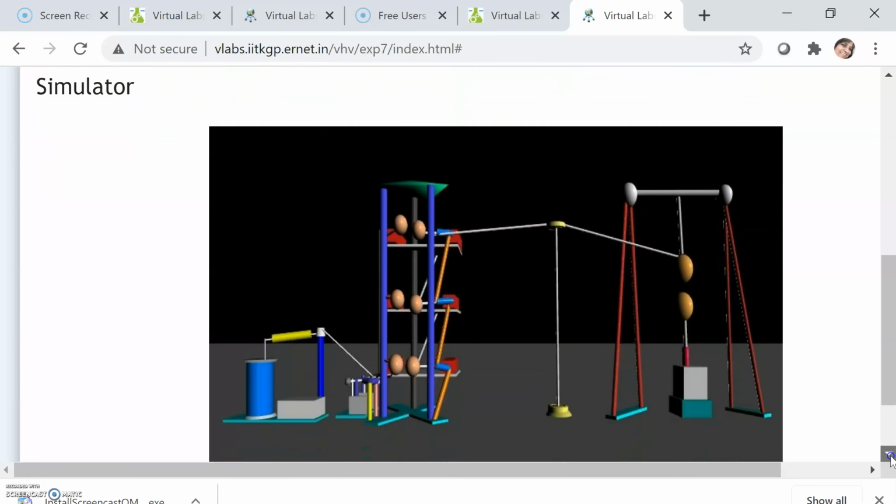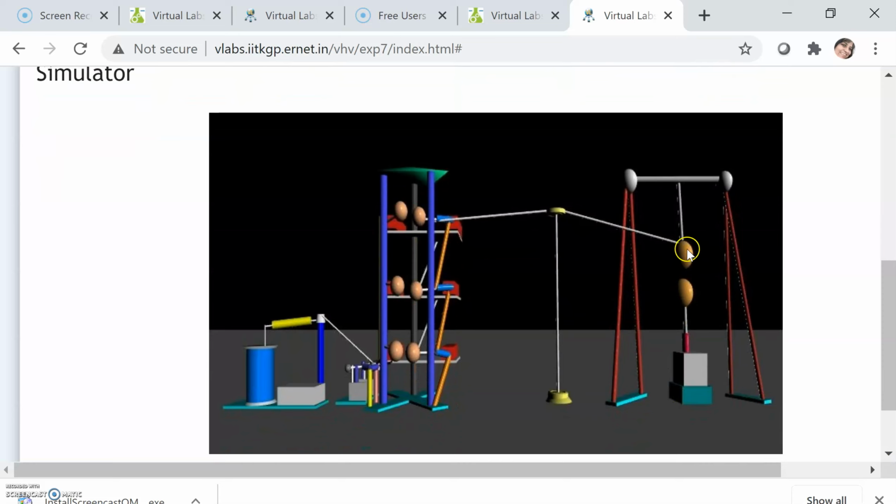If you see this apparatus, you now know the sphere gap and the voltmeter. This is a sphere gap. Two spheres are separated with air as an insulating material. And we have discussed how to find out the dielectric strength of air. So keep the gap distance between electrodes 1 centimeter, 2 centimeter, 3 centimeter or any, and apply high voltage using a step up transformer.